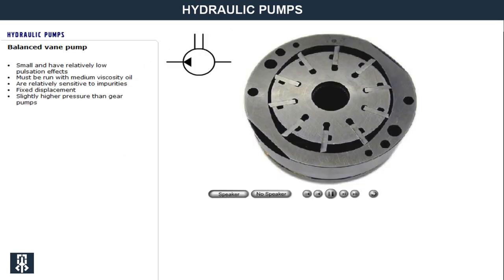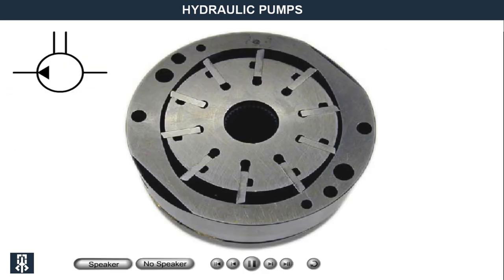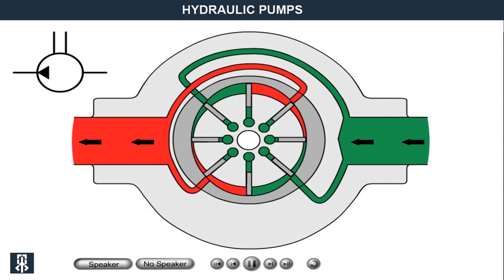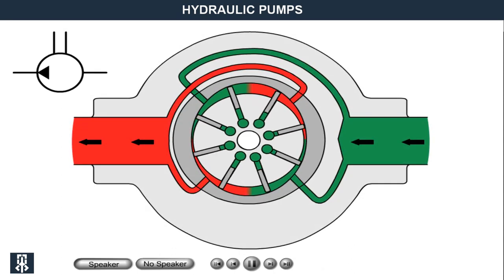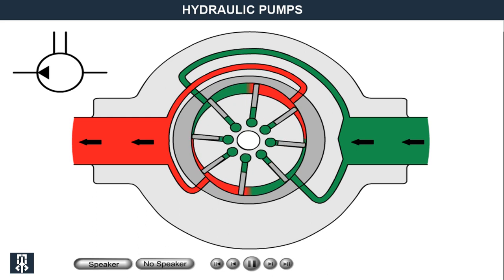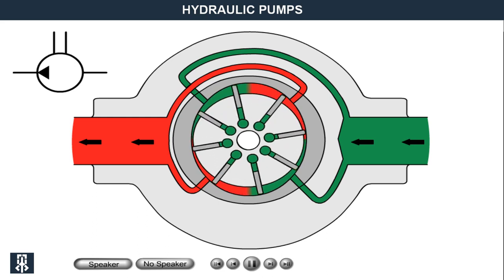Balanced vane pumps have a cylindrical rotor with radial grooves where freely movable vanes are placed. The rotor is placed in the centre of an oval pump housing, which has two inlet and outlet channels. One gets an even load of the rotor bearings, which is why this type of vane pump is called balanced. When the rotor works, the vanes are thrown out against the pump housing's walls and bring oil along.